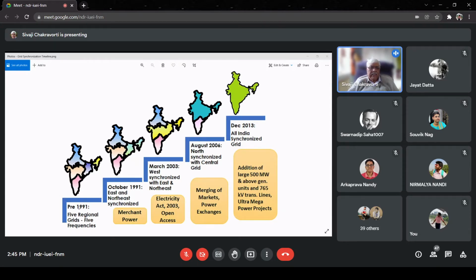As you can see, pre-1991, that means up to the end of the 1980s, the Indian power sector was divided into regional grids, not any national grid. And you will be surprised to know that these grids were not synchronized. That means one grid may operate at 49.8 hertz, another may operate at 51.2 hertz, and so on. So they were all segmented, individual regional grids. But a lot of discussion was held that this should not be the case, so a lot of efforts were put in to synchronize these regional grids.